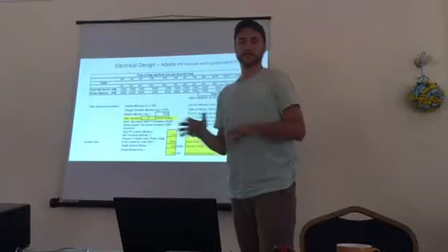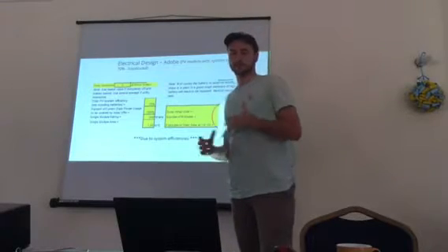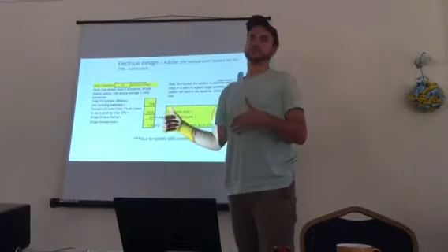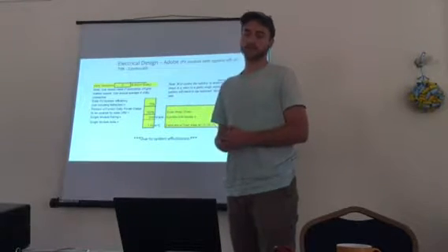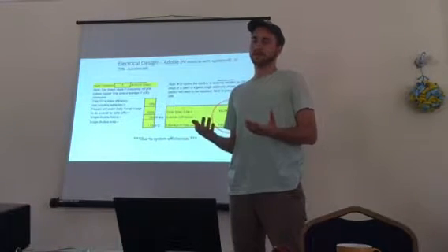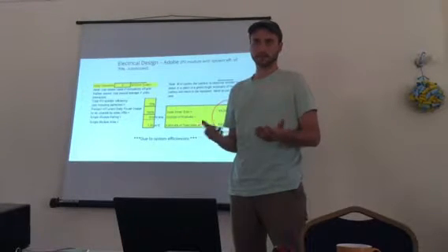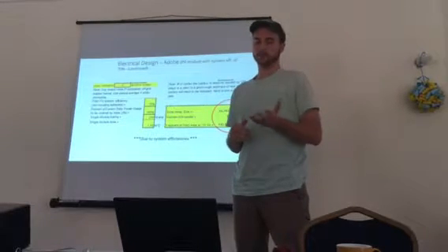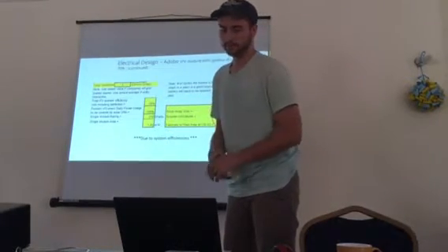So the overview calculation for total demand per day basically boils down to the following, and that is a solar array size of about 15 kilowatts. That's including all the inefficiencies of the system, boiling down to your 6,000 watt output capacity on the other end. So factoring around 250 watt panels, which I found a 24 pack in Lusaka, which actually had an 80% efficiency rating for 20 years. Again, I used a 70% efficiency rating to be safe. We came out to about 63 modules for the Adobe site, which would equate to about 140, 150 square meters.